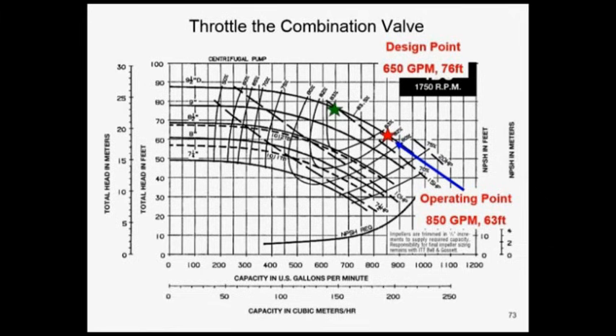So we could throttle the triple duty valve or throttle the balancing valve. A little yellow line should get you back up there. And I've added pressure drop to the system. I've changed my system curve. My system curve was actually 63 feet, but I'm going to add some pressure drop through this throttling valve. I'm going to push it back up to 76 feet. Now I'm at 650 GPM. I'm now back at design.